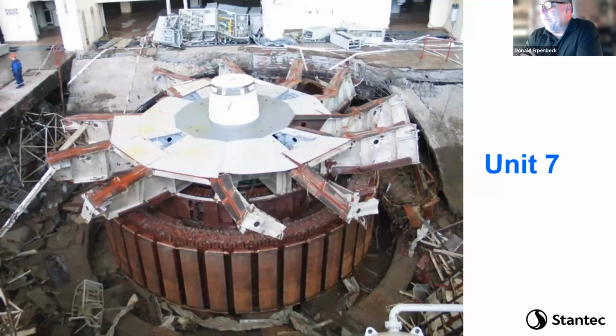The frequency will begin to deviate, and at about half a hertz the breakers of the system will begin tripping. So at about 50.5 hertz and 49.5 hertz, the rest of the system will begin to disconnect the grid from the rest to protect itself. To deal with the varying loads, you put a machine, typically a hydro machine because they're the best machines for ramping, in AGC mode, and it follows the load and tries to maintain, in this case, 50 hertz on the node. If the frequency begins to go up or down, it adjusts the power output up or down to match. So that is what AGC mode is, and it's happening automatically with no operator decisions. It's simply watching the frequency.